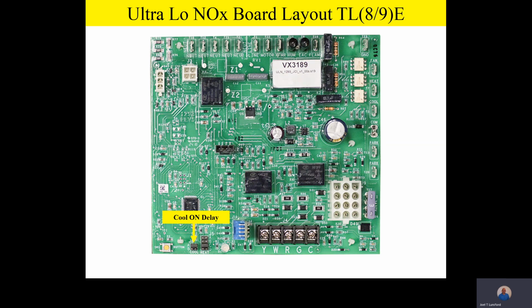For 24 seconds, it'll delay the fan coming on, and so the outdoor unit will come on. It'll pre-chill the evaporator coil to allow better dehumidification every time you have a cooling call. So this is a nice little dehumidification function that you can manipulate in the field. A is 6 seconds, B is 24 seconds on our cooling on delay.